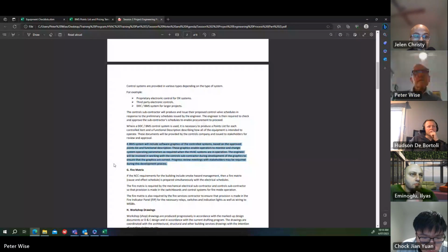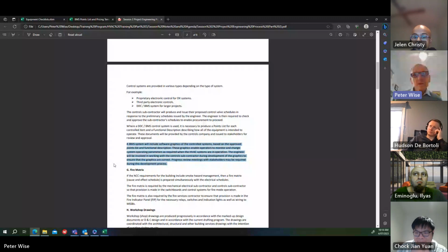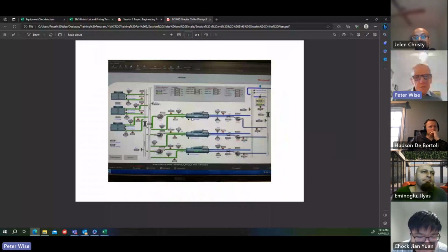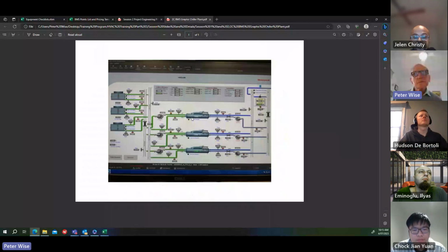This is a chiller plant graphic, not very clear, but on site this comes up on the operator's screen, or you can look at it remotely if you have remote access. You can see various numbers, the set point and the actual operating point. Depending on what access is available, you can go into a particular point and make an adjustment, for instance changing a value from 7 down to 6. It's a way for operators on site to monitor and make adjustments if they want.